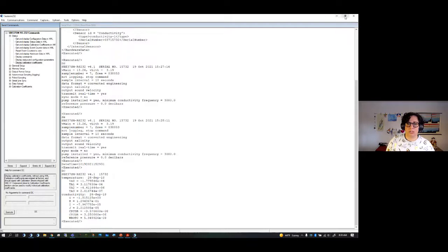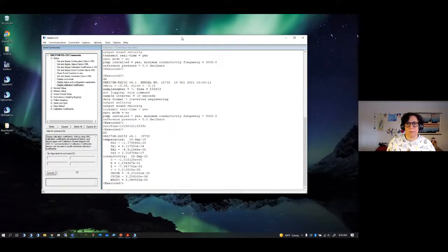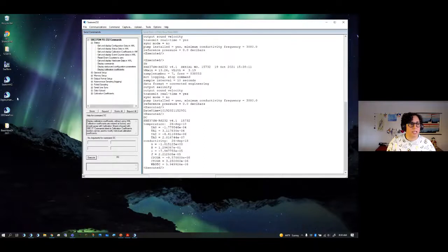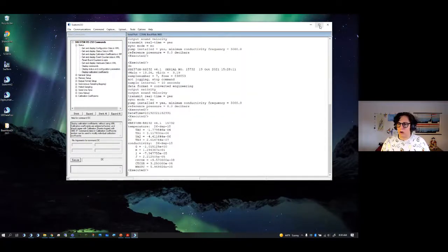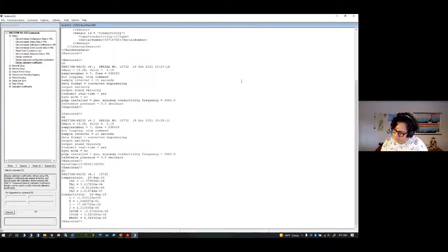And so the way that you do this is, I'll scroll this back up and zoom back out. I have my calibration sheets, but I guess I had uploaded them last night. If you look on the calibration sheets, you'll get it as a PDF, and you will be able to compare that. So these do match my calibration sheet. I'm sorry, I don't actually have it right here. Let me just check if it's in this folder. Nope, okay. All right, so you've checked your calibration coefficients here.